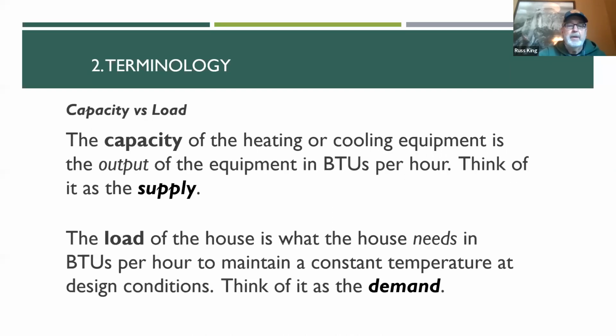Okay. So capacity is the ability of the heating equipment to provide heat or cooling. It's rated in BTUs per hour. Think of it as the supply. It's what you get from the equipment. And then the load of the house is a calculated number, and it's how much heating or cooling the house needs. So think of that as the demand. So you've got supply from the equipment and the demand of the house.